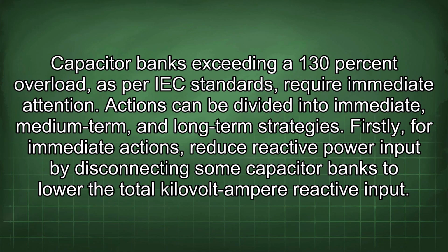Capacitor banks exceeding a 130% overload as per IEC standards require immediate attention. Actions can be divided into immediate, medium-term, and long-term strategies. Firstly, for immediate actions, reduce reactive power input by disconnecting some capacitor banks to lower the total kilovolt-ampere reactive input.